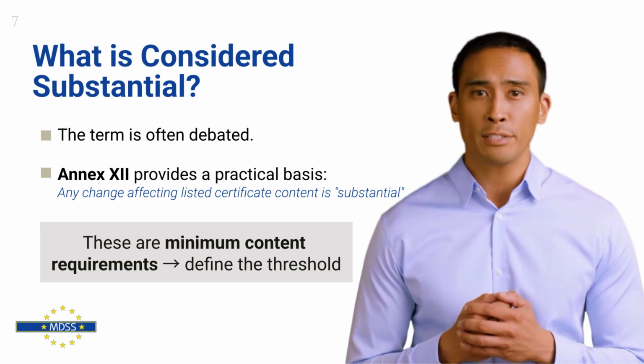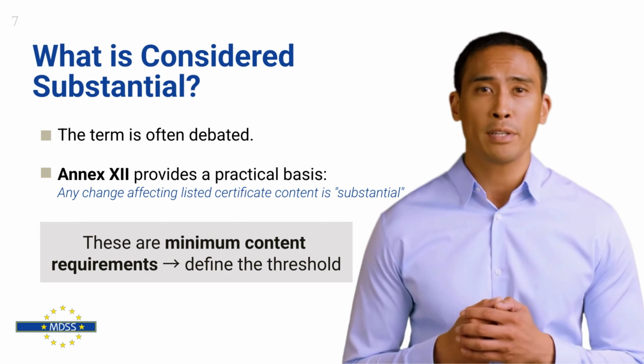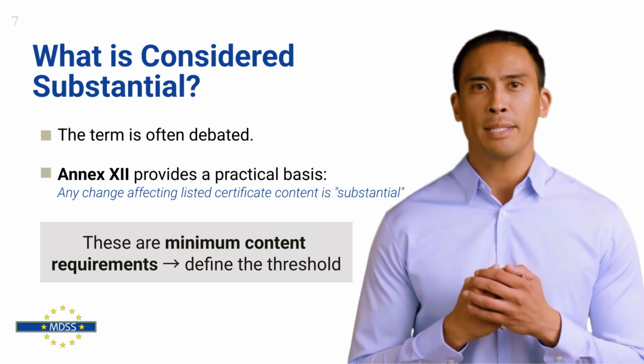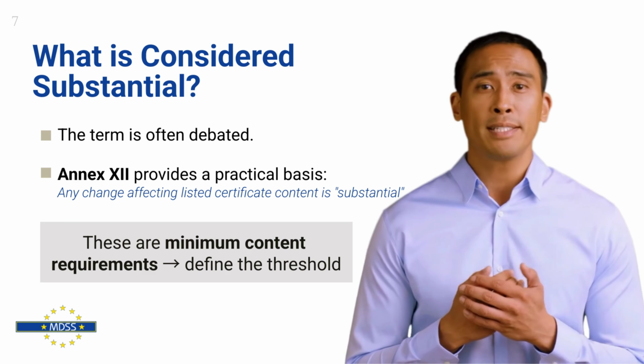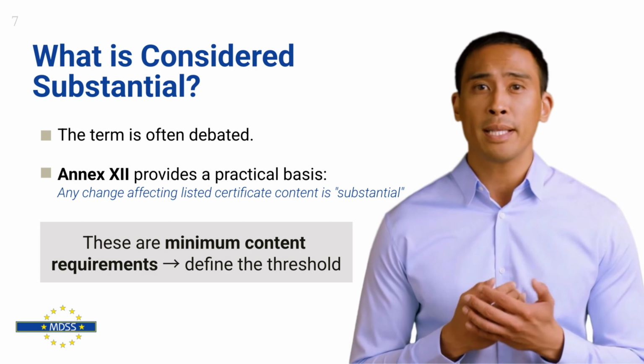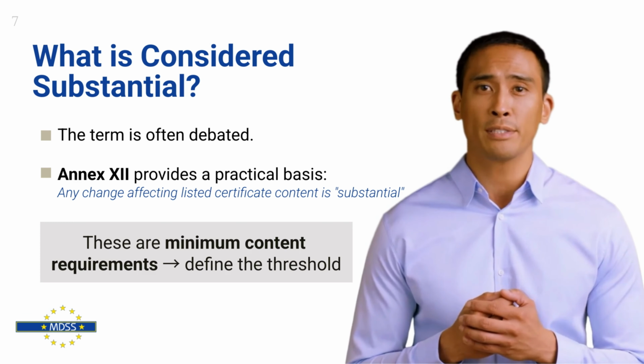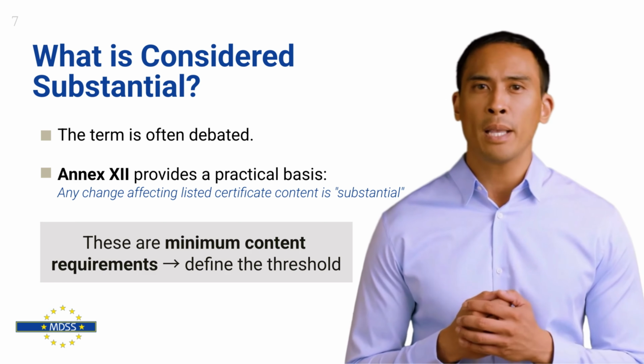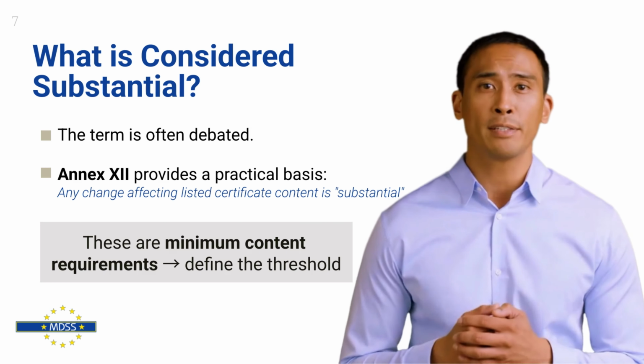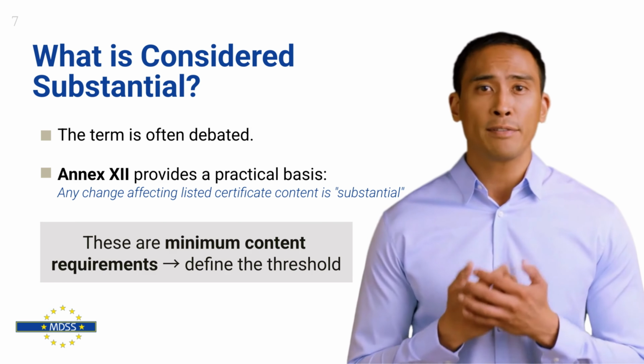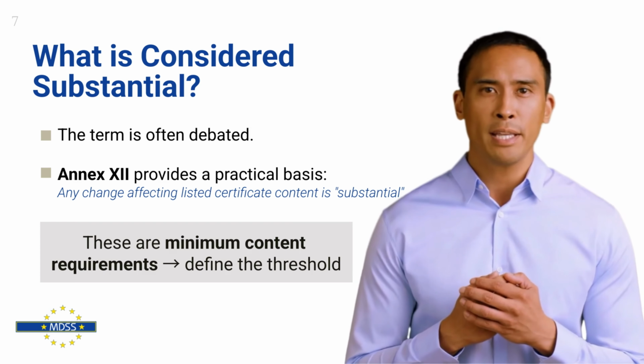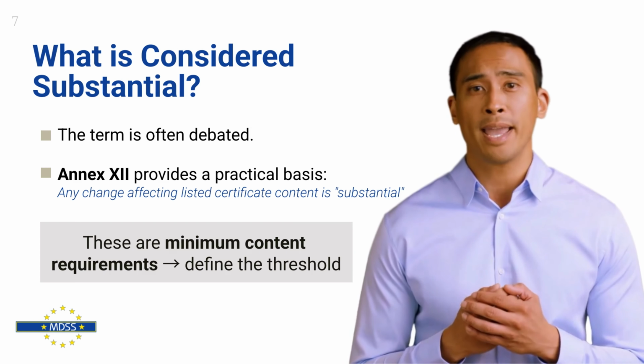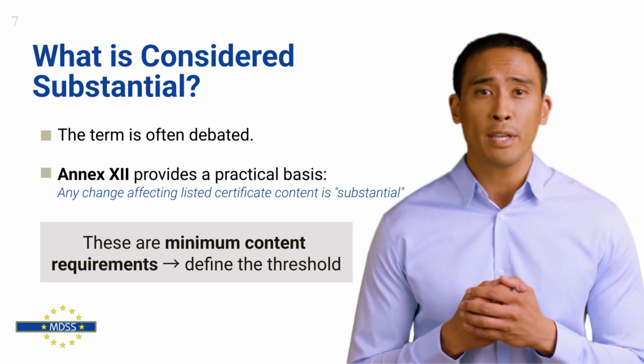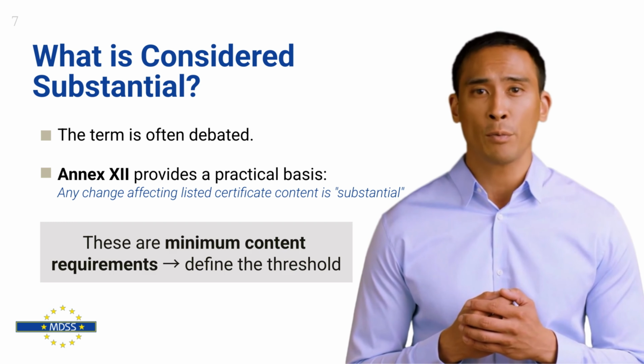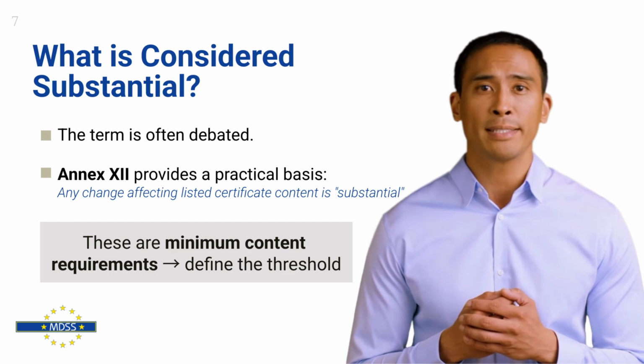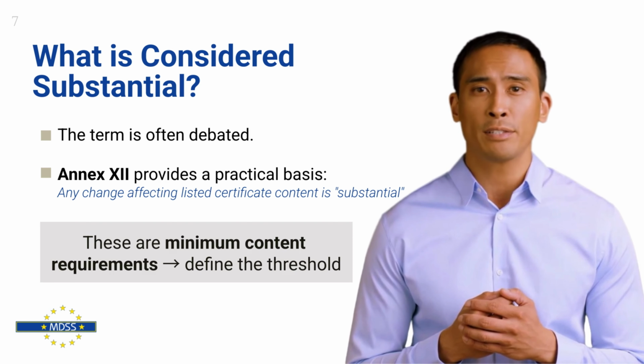Clarifying the debate around the term substantial. The term substantial is often subject to debate. However, when the process described in the MDR is respected, it becomes clear which changes truly qualify as substantial. Only those changes to the quality management system that have an impact on the certificate itself are to be considered substantial. This clarity is supported by Annex 12, which outlines the minimum content of the certificate.